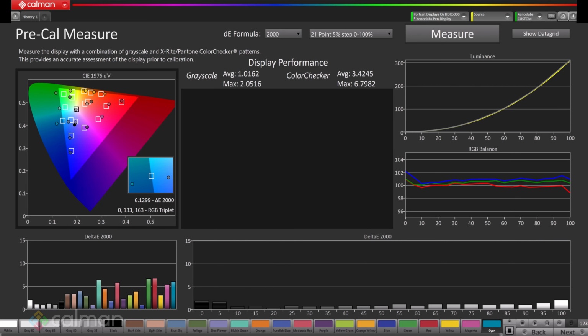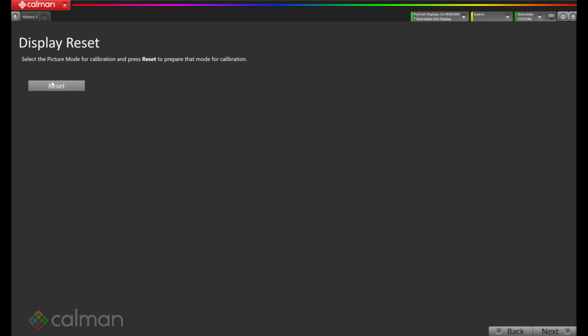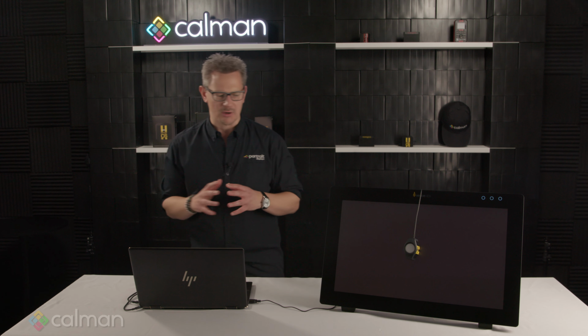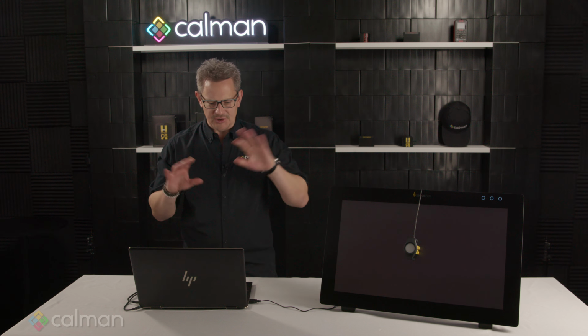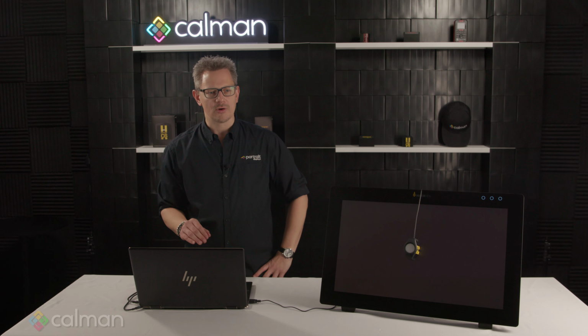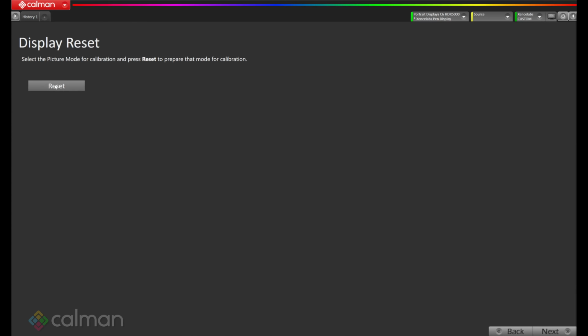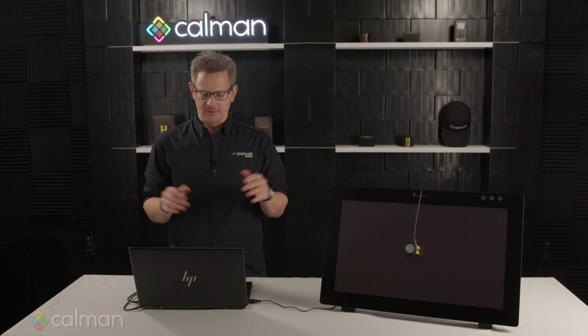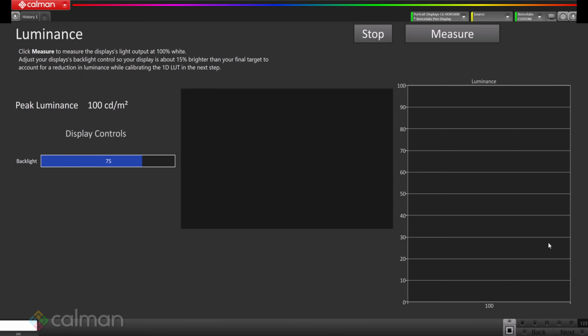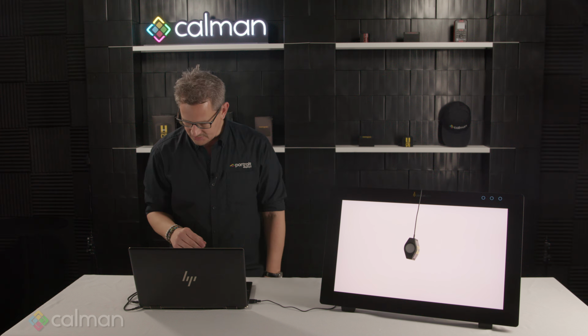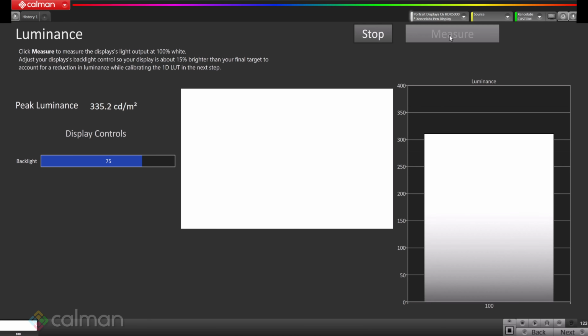So I click next, and the first thing we do is a display reset. That means any setting that was probably still in the memory of the video processor is reset back to the original factory state. And after this, we can start the calibration. All right, the display reset is accomplished. Now we click next. Here we can check the display luminance, the peak luminance of the display. If I click measure, it shows how bright the display is at peak white. Now we are around 335 nits, or candela per square meter, which is the same unit. And since it's an LCD, an IPS panel, we can change the backlight here with the backlight control.